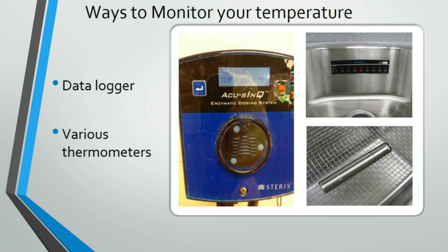So that's why the thermal disinfection happens in the rinse, and it can't be counted on in the dry cycle. There are some really easy ways to monitor water temp. ST79 says we should, so how can we? You can go with something digital, happens to be a little dosing system there, but that dosing system also has a digital thermometer that reads the temp for you.